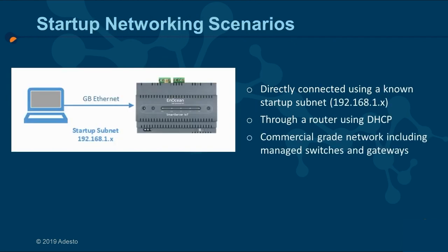Out of the box, all of these scenarios work for the Smart Server IoT. You could connect directly through an Ethernet cable and configure your PC to be on a known subnet 192.168.1, provided it does not conflict with the Smart Server's 192.168.1.222 address.